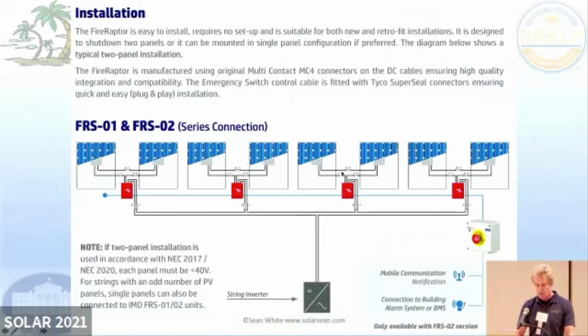Sometimes you'll see 2 modules in series. That doesn't comply unless it's 3741 or one of those exception ways. That's not module level shutdown if you have 2 modules in series. So just beware of that.